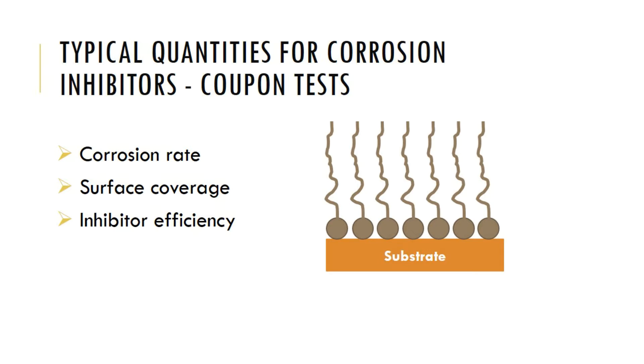These quantities are related to how well the molecules of the corrosion inhibitor settle on the substrate, as shown in the figure in this slide. These quantities are usually calculated by performing coupon tests in stationary electrolytes, which means that the coupons are inserted inside the electrolyte and the corrosion rates are measured depending on the weight loss that happens over a certain period of time.